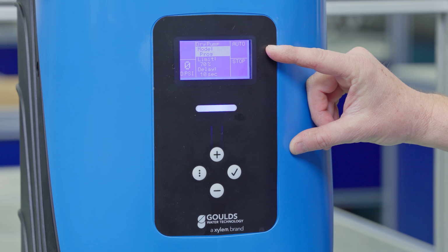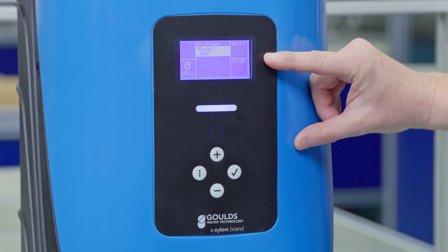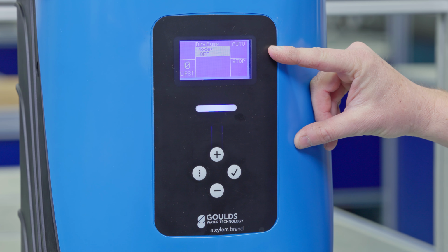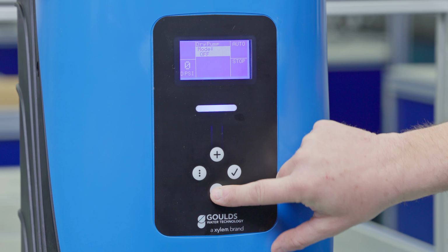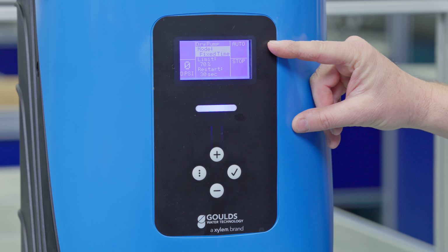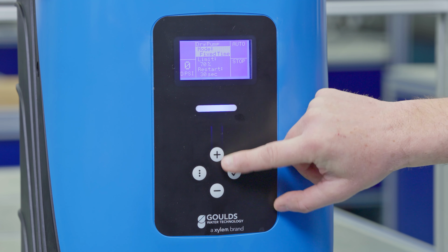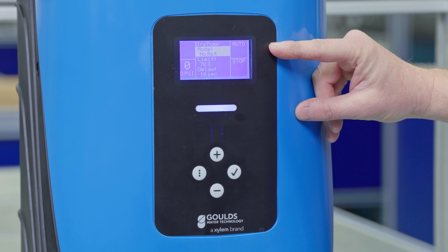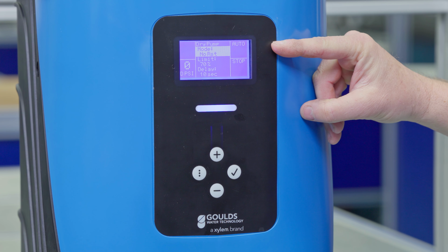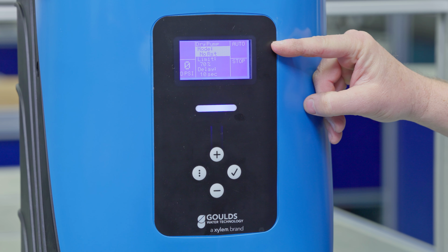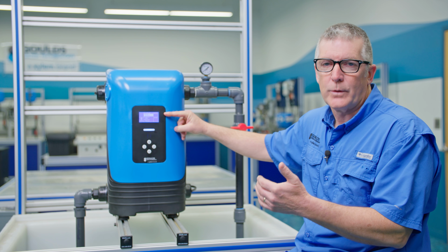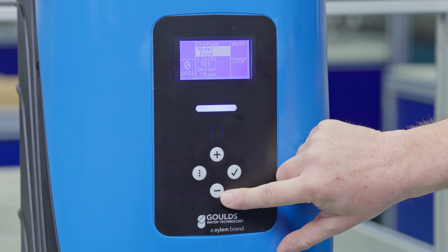What options do we have? So we're going to hit the down button. So you could turn that dry pump protection off. That's an option. We could put a fixed time in there. That's another option in terms of the restart. When do you want this thing to restart? And you can put your own fixed time in there. So that's an option. The other is no restart. And so that means that if it trips off on dry pump, then it will not try to restart, and there has to be a manual restart for that. So those are your options.